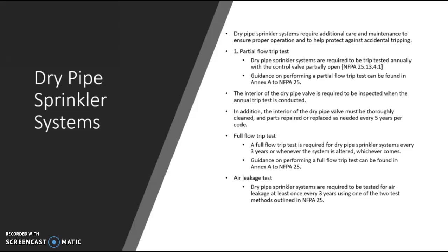We want to make sure that it's tested annually with the control valve partially open. Guidance on performing this can be found in Annex A, which is located in NFPA 25, to go on through it. The interior of the dry pipe valve is required to be inspected when the annual trip test is conducted, and it must be thoroughly cleaned every 5 years per code. A full flow trip test is required every 3 years, or if the system is actually altered in any way, it's required to be done as well. Guidance on performing that can also be found in Annex A of NFPA 25.